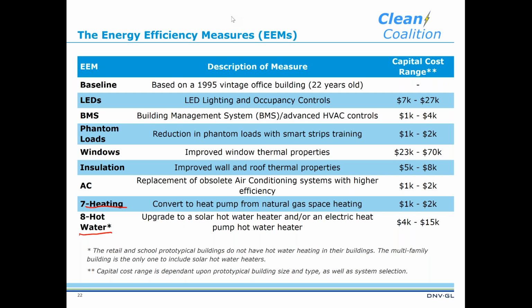I want to point back to the example of Norway—they're using electricity to heat all their commercial buildings, so it's definitely something that's possible. What you'll run into if you try a direct replacement from a gas system sometimes is a requirement to replace ductwork—it really depends. The issue is that natural gas heating systems often supply heating air above 110 up to 130 Fahrenheit, whereas a heat pump will supply heat at 90 to 100 degrees Fahrenheit. Really good question—Norway's doing it, and they're really leaning on heat pumps to make that happen.